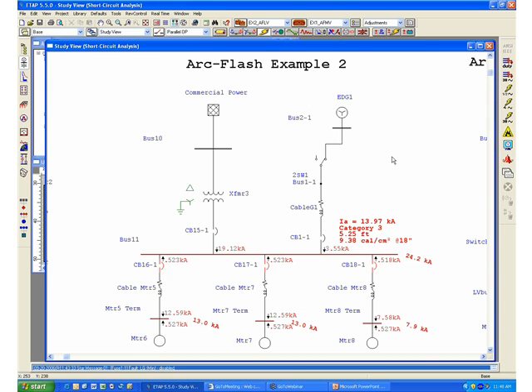In ETAP, you could set up unlimited number of configurations and study cases to study many operating conditions in your system. It's very important that you actually consider all the different operating conditions in order to determine the worst possible incident energy.